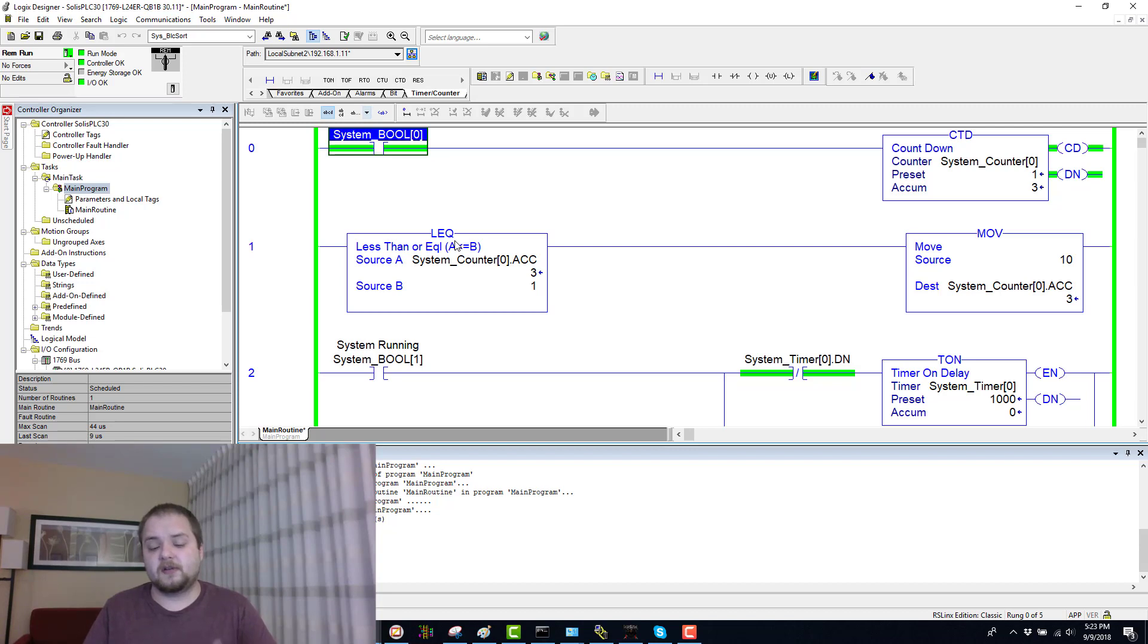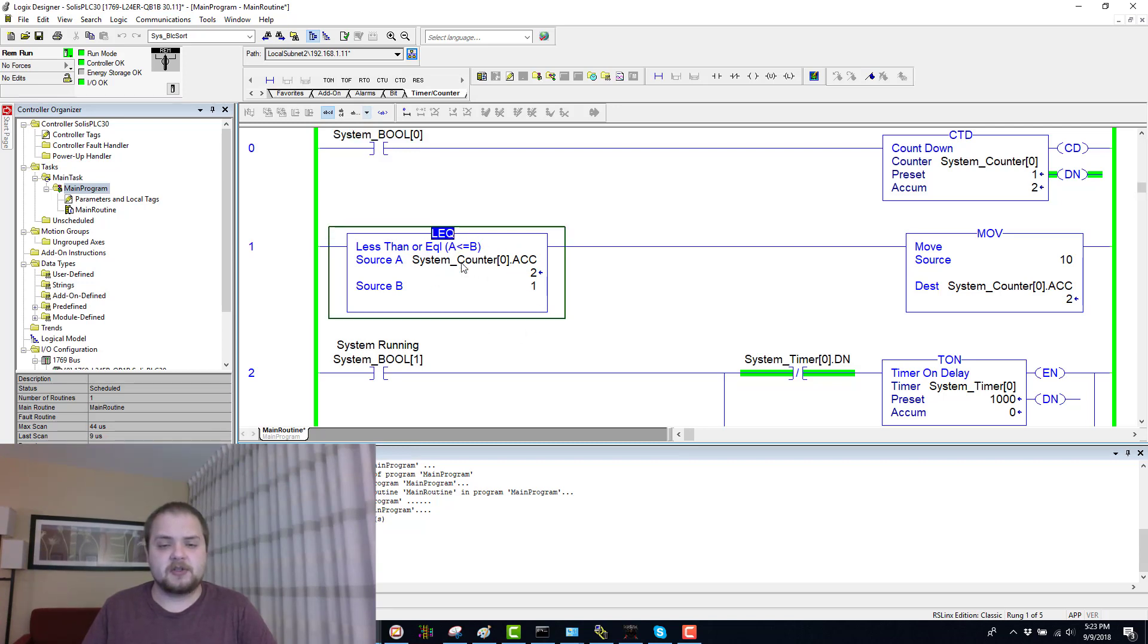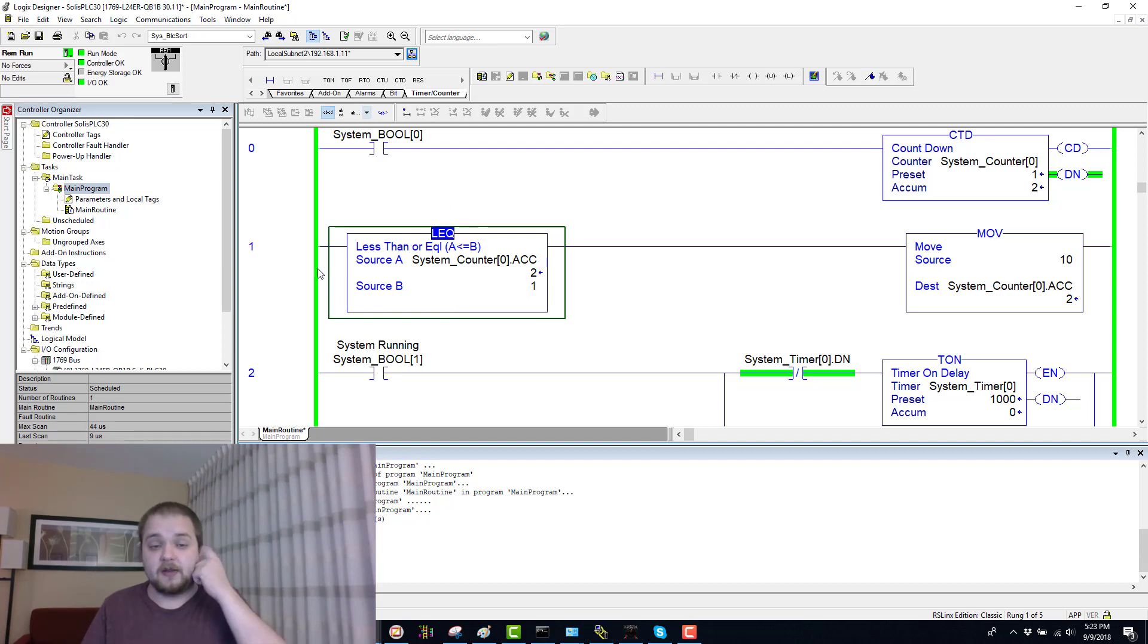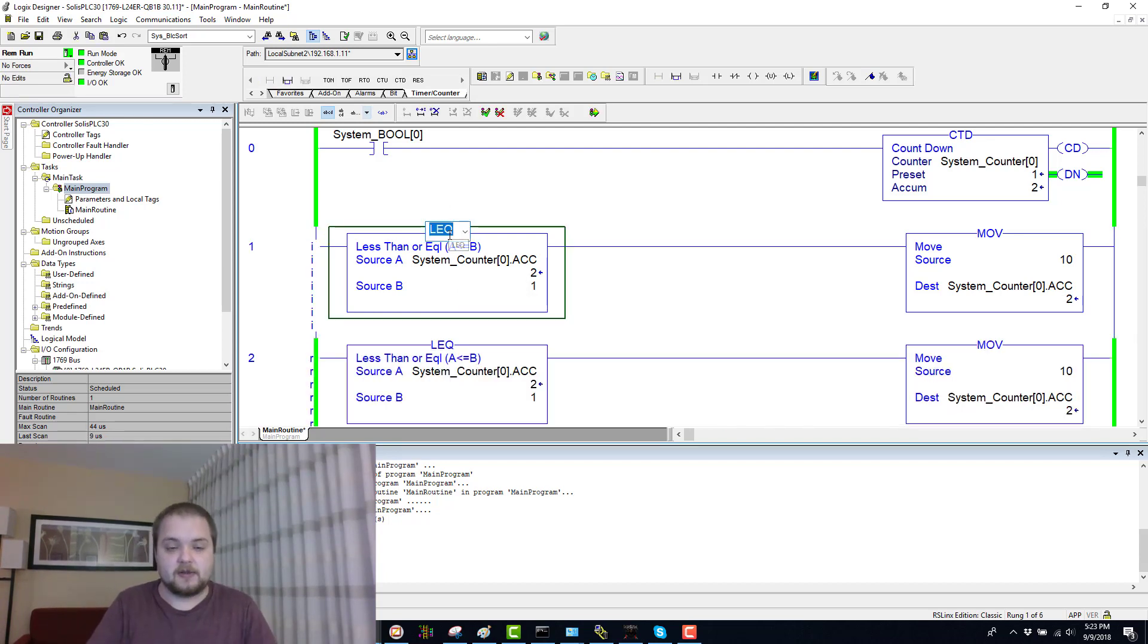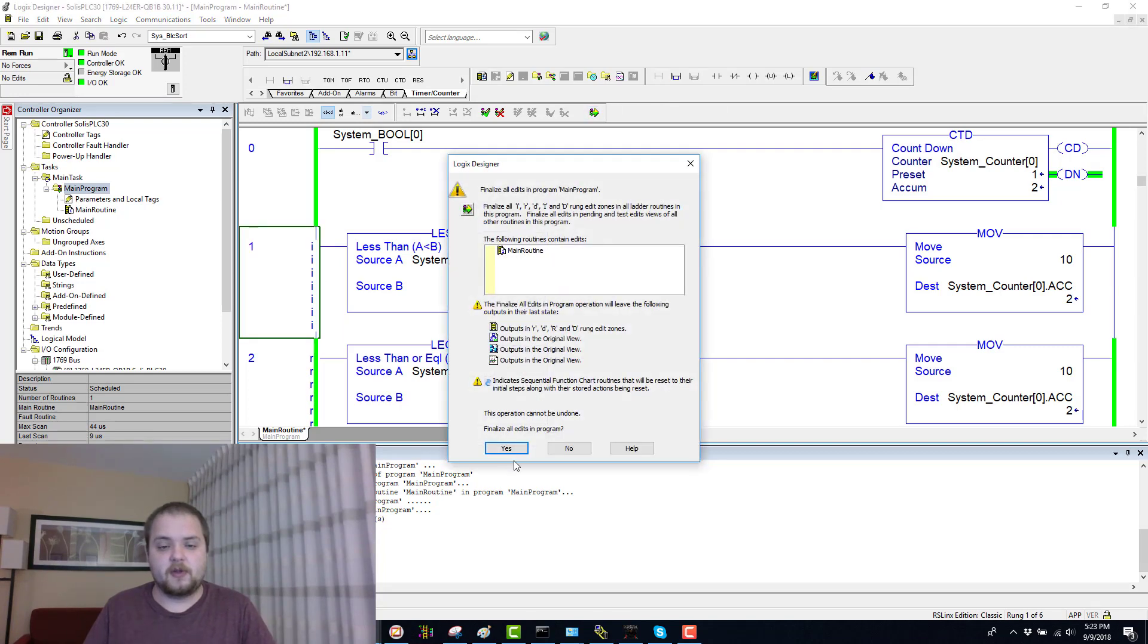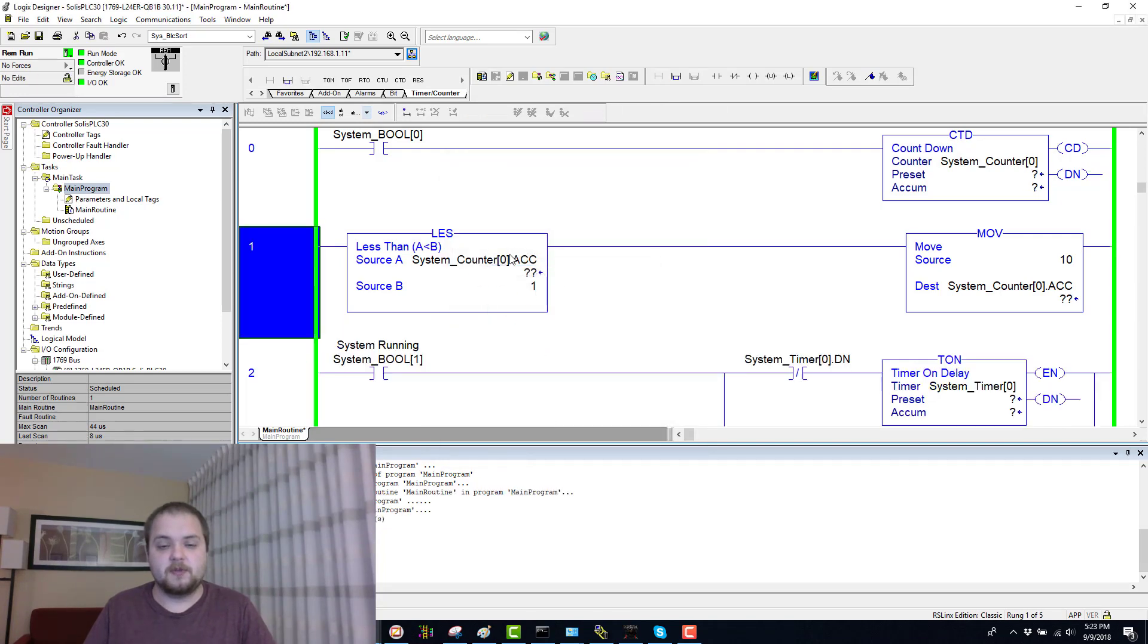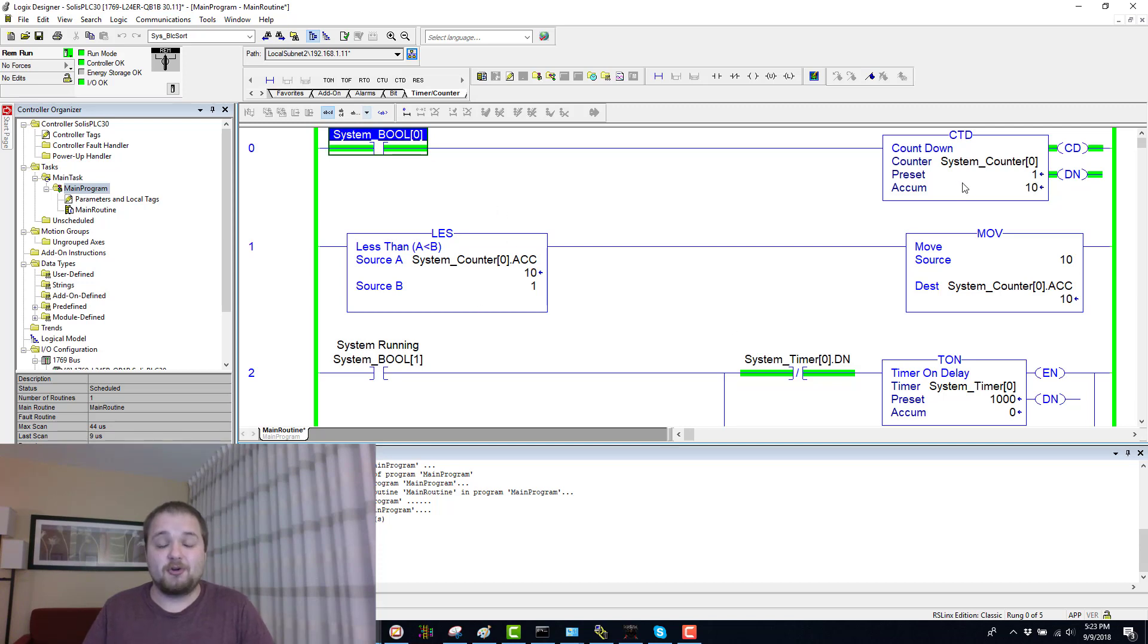In this case, I would not necessarily look for a done bit but I would look for a condition as to where this accumulated value is less than. Here I did mention that less, but it's less or equal to, so it's an LEQ instruction versus an LES. I'll change that to an LES, compile the whole thing. This should be less than one. As soon as we toggle that one more time, it goes back to that 10 value as explained before.